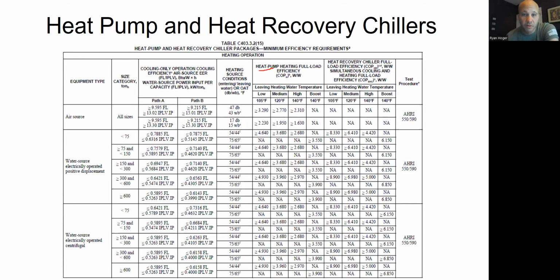heat pump or heat recovery. So 2 different sections in here. Each of them has 4 columns. So let's say you have the heat pump. That means you're going to have a refrigerant reversing valve inside the chiller. And it's very similar to what we did before with the hot water boiler and so forth. In fact, that hot water boiler that I described in the last module, it would have to comply with this table too, under this heat pump heating efficiency.